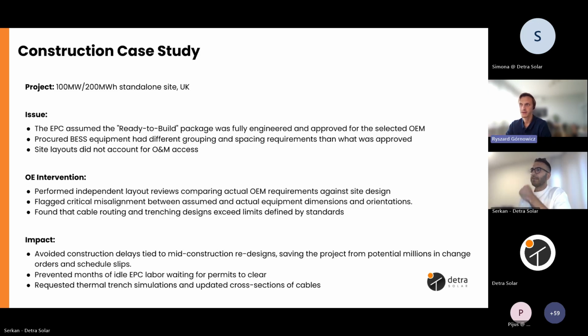We also uncovered that cable trenching designs exceeded grouping limits defined by IEC standards, which is a fairly common situation on tightly packed sites. This single fact, if left uncovered, could have led to overheating, performance losses, and even failure down the line.